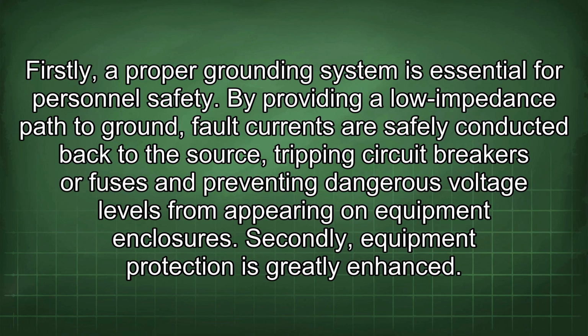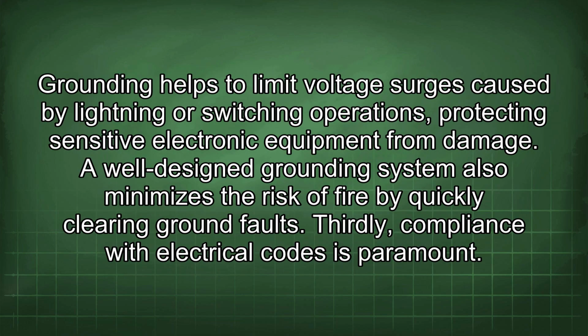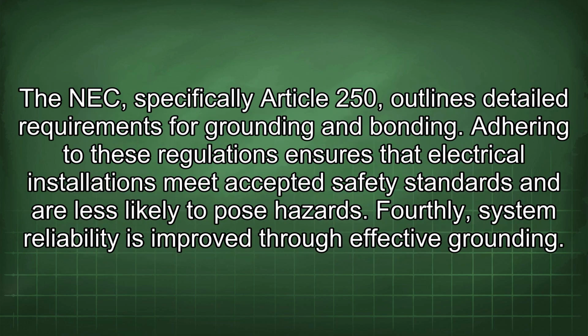Secondly, equipment protection is greatly enhanced. Grounding helps to limit voltage surges caused by lightning or switching operations, protecting sensitive electronic equipment from damage. A well-designed grounding system also minimizes the risk of fire by quickly clearing ground faults. Thirdly, compliance with electrical codes is paramount. The NEC, specifically Article 250, outlines detailed requirements for grounding and bonding. Adhering to these regulations ensures that electrical installations meet accepted safety standards and are less likely to pose hazards.